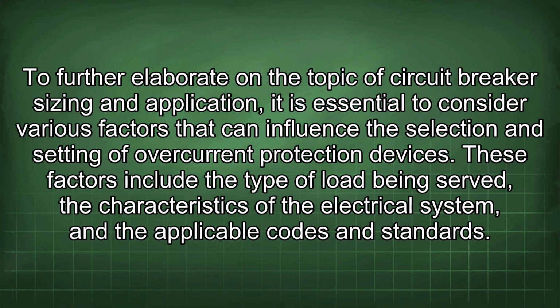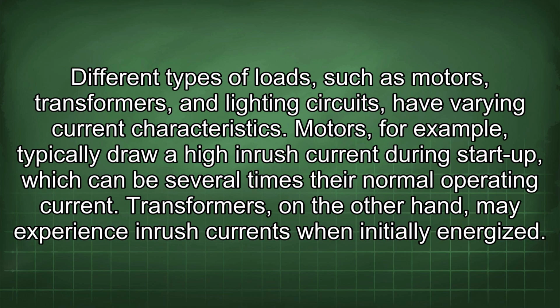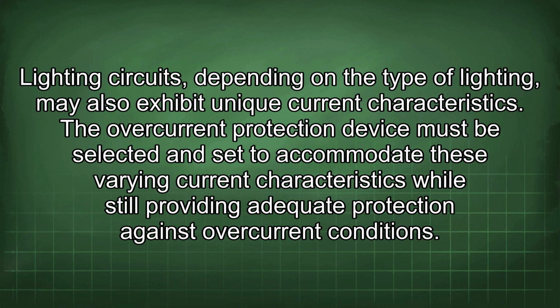These factors include the type of load being served, the characteristics of the electrical system, and the applicable codes and standards. Different types of loads such as motors, transformers, and lighting circuits have varying current characteristics. Motors, for example, typically draw high inrush current during startup, which can be several times their normal operating current. Transformers, on the other hand, may experience inrush currents when initially energized. Lighting circuits, depending on the type of lighting, may also exhibit unique current characteristics.